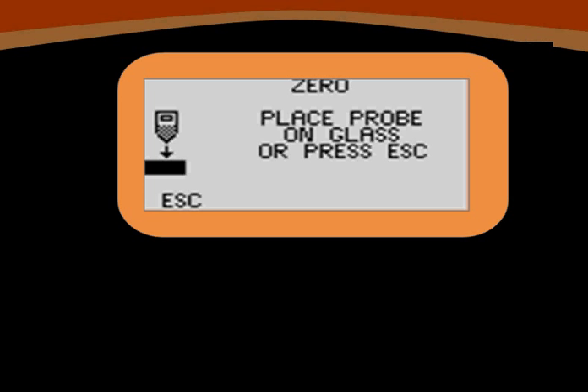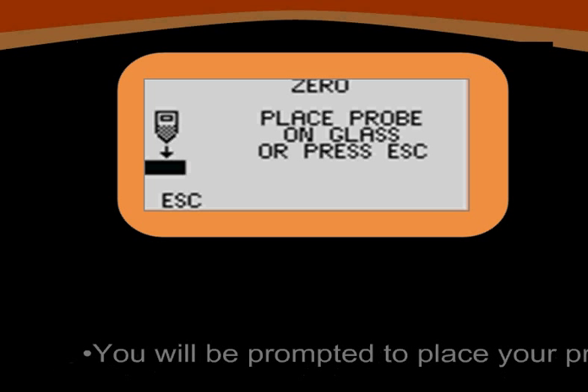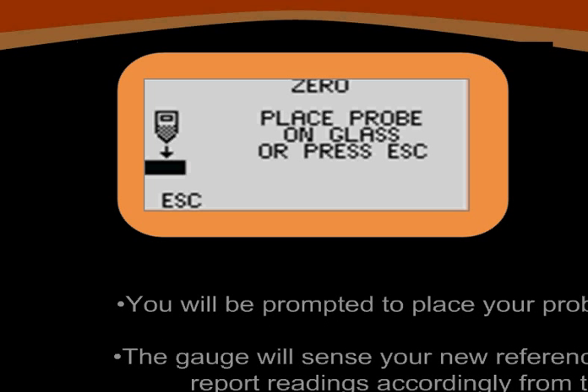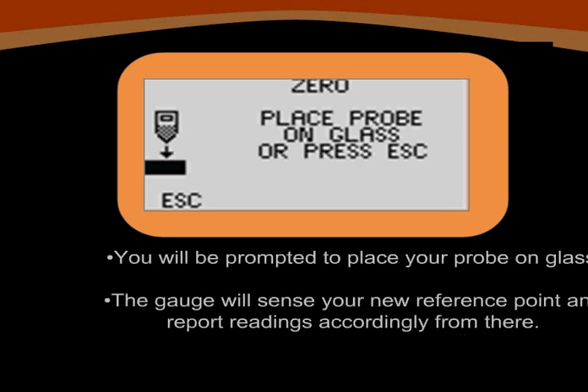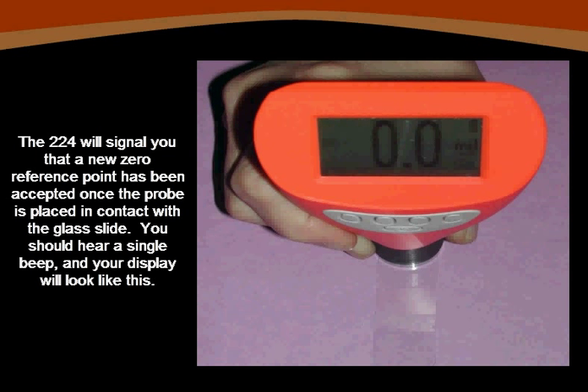To calibrate or recalibrate your gauge, select zero from the menu. Place the probe on the glass slide provided with your 224 to obtain an accurate zero. Once you have successfully calibrated, your display will look like this.